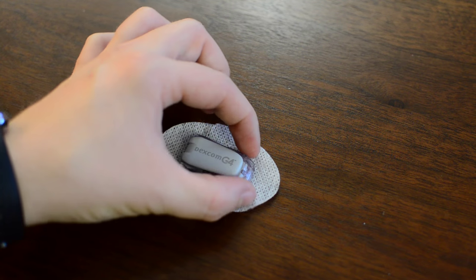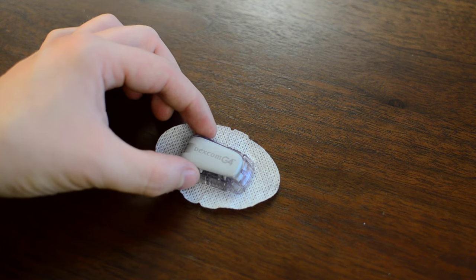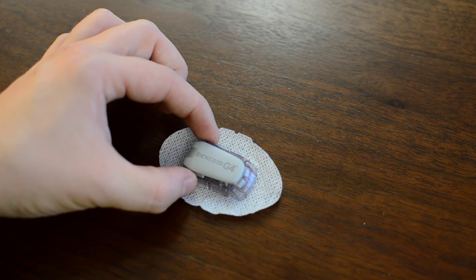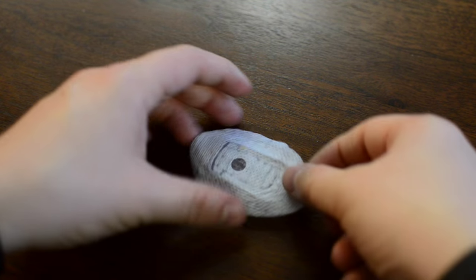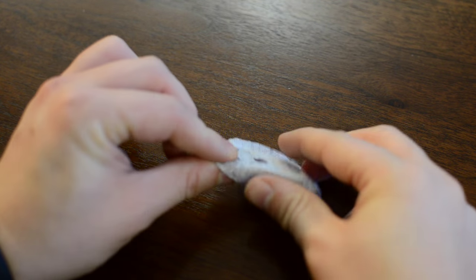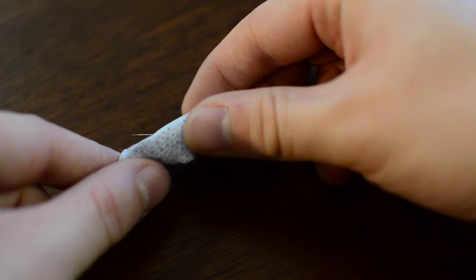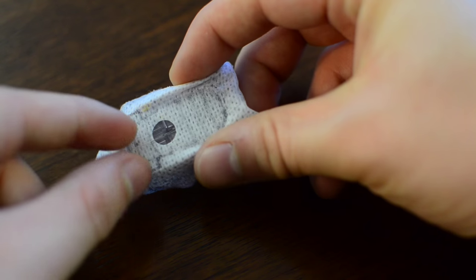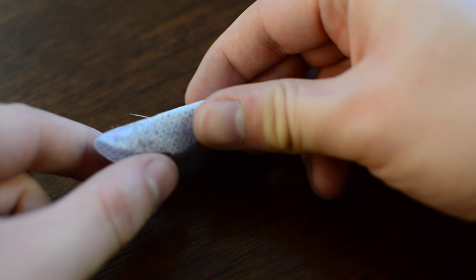So here we have an actual sensor. I went and put it together so we can see what it looks like. We have the adhesive around the edge. It is pressure sensitive, and you do want to start closest to the sensor and just push out and brush out and make sure that there are no overlapping areas as you're adhering it. As you can see on the bottom, it's really hard to see, it's super tiny, but there is the piece of metal in there that's actually your sensor.